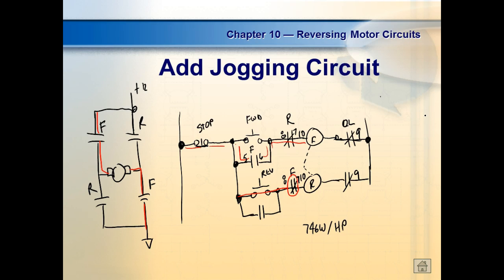Right? I understand that. But what's the mistake somebody here is going to make? They're going to look at the same relay. I'll come up here and check L2, and I didn't put my dot right there. I come over and check L2. I say, okay, you can put power on it, you go over there and you press forward, and that relay chatters. You can understand why, right? As soon as you hit it, F picks up. As soon as F picks up, F drops the relay out. As soon as it drops out, it just sits there. Everybody's going to turn around and look at you. And everybody needs to laugh, right?